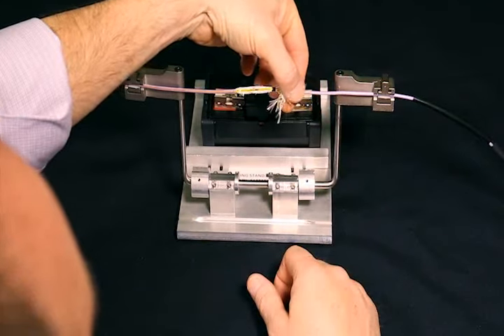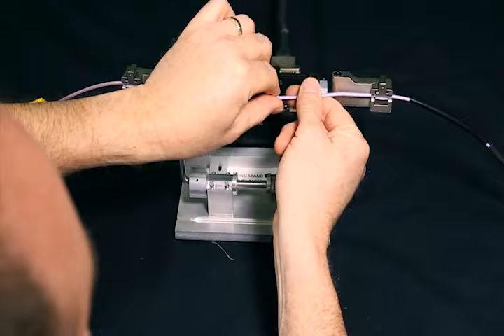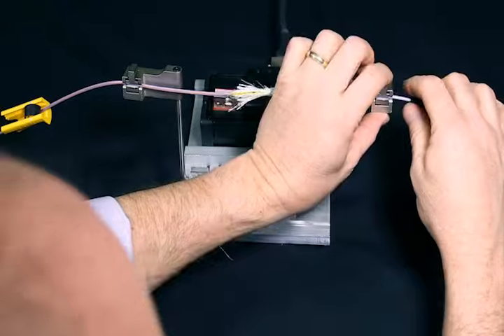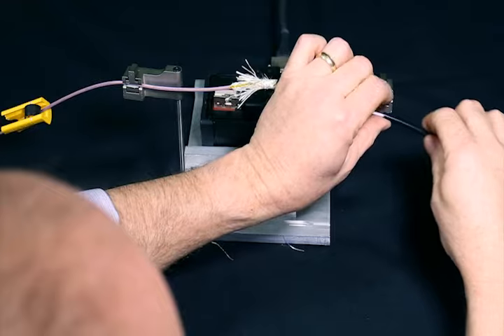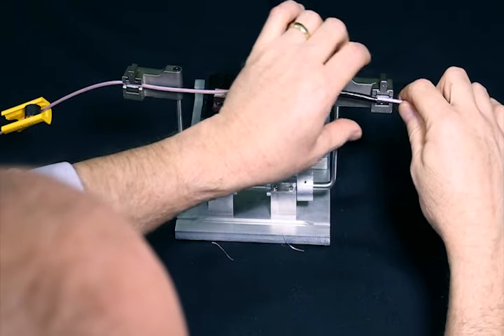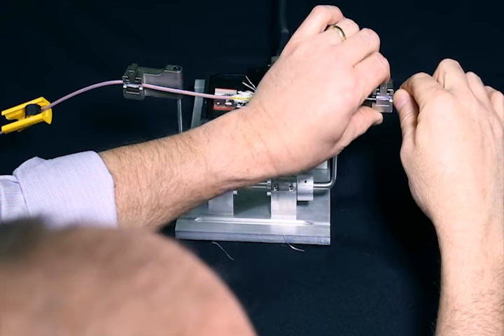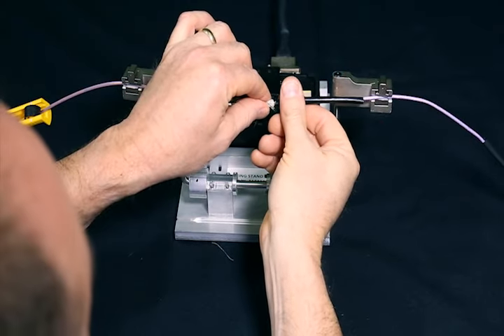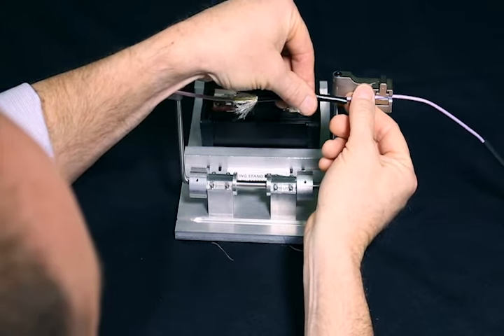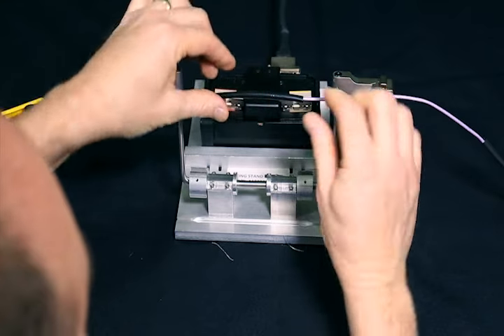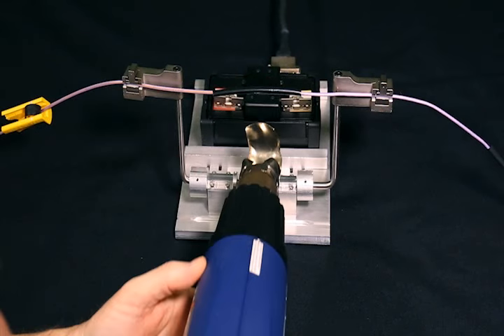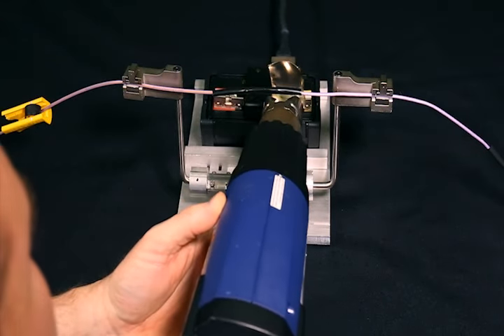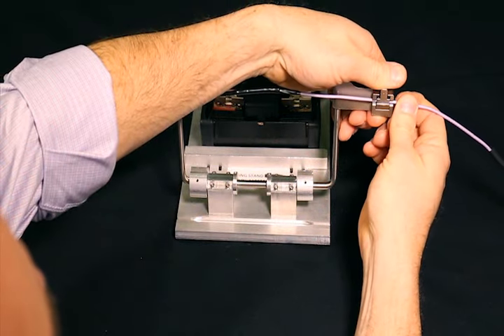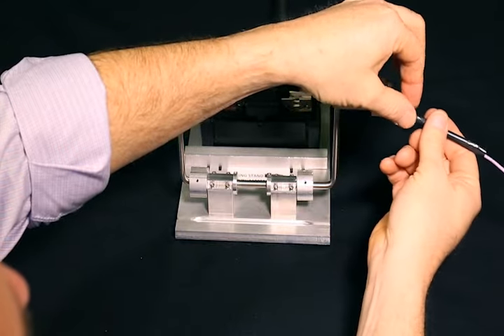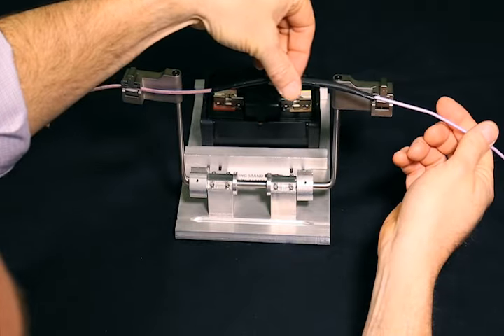Shrink the clamp ring with the heat gun, then allow to cool. Slide the integrated secondary sleeve past the clamp and over the braids and center it. Be careful not to let the cable bend while it is not clamped. Shrink with a heat gun and allow to cool.